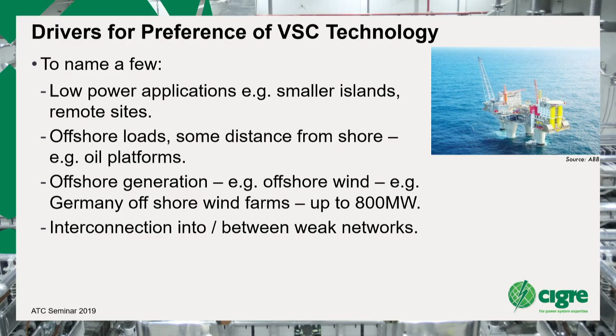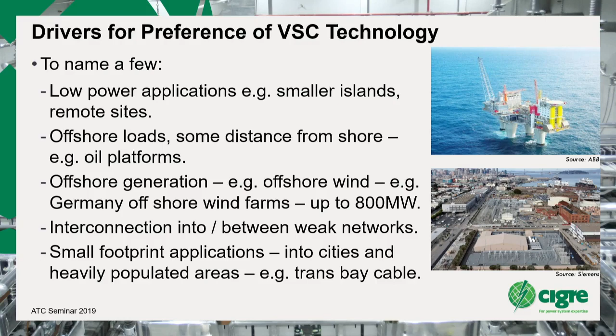The other thing I really like about VSC, which would take a whole presentation to explain fully, is that generally they have a smaller footprint. With an LCC converter, the majority of the footprint is actually just AC filters, because you have to feed LCC with reactive power as well as control the harmonics. With VSC, there's a good chance you won't need any filtering.